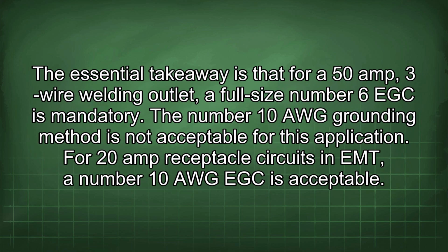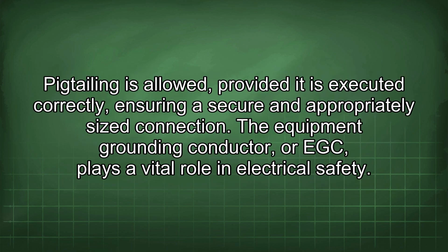The essential takeaway is that for a 50 amp 3-wire welding outlet, a full-size number 6 EGC is mandatory. The number 10 AWG grounding method is not acceptable for this application. For 20 amp receptacle circuits in EMT, a number 10 AWG EGC is acceptable. Pigtailing is allowed, provided it is executed correctly, ensuring a secure and appropriately sized connection.